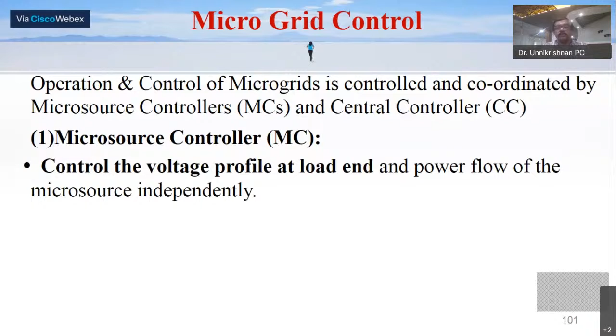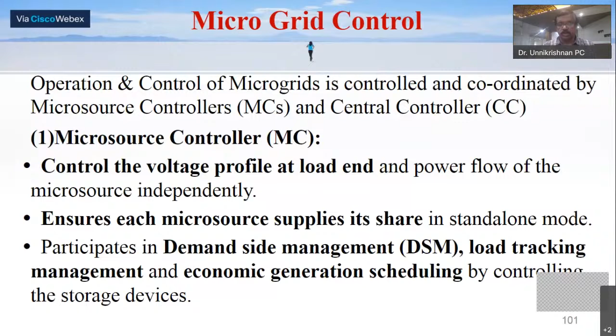The micro source controller is the controller attached to each and every distributed generator. It controls the voltage profile at the load end and the power flow of the micro source independently. The micro source controller will be connected with the central controller, and it should ensure that it supplies its share in the standalone mode. Whenever there is an islanding, the central controller will ask a specific micro source to generate a certain amount of energy, and the micro source controller should see that this energy is supplied. So there is a coordination between the central controller and the micro source controller in balancing the generation and the demand.